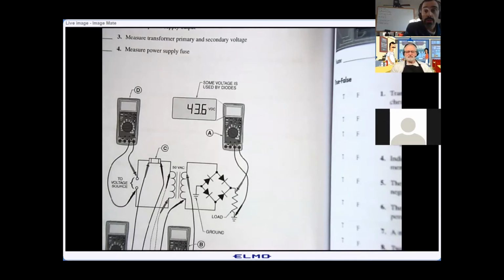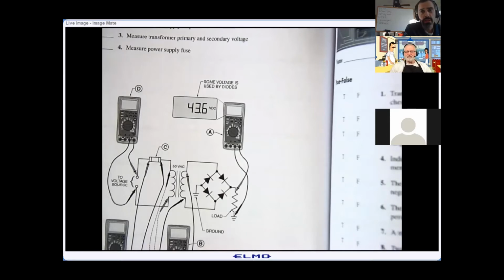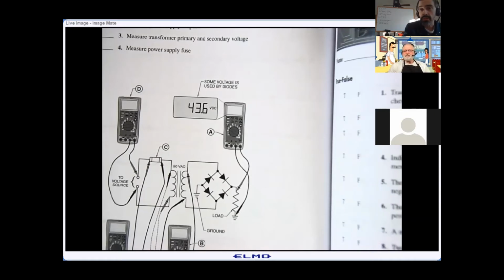Okay, input. To be honest with you, I break it into what I call segments. I do start with the input side, but I assume that the input side consists of pretty much a transformer. Not too likely that my transformer would go out unless you really beat on the thing. I mean, the transformers are meant to take a lot of abuse. If it's supposed to handle 20, 30 amps, it's going to handle 20, 30 amps. So pretty much input is just a quick glance to make sure none of the wires melted, first of all. Okay, no wires melted. Now I'm going to break it up. I'm going to say the transformer is good at this point.